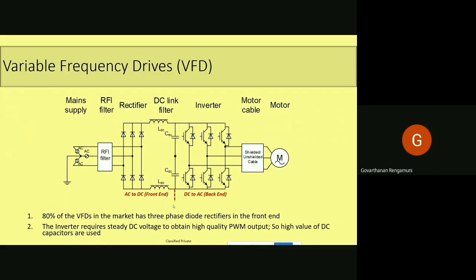The figure shows a typical variable frequency drive, and here different sections of the drive are noted. You can see the variable frequency drive derives the power from the mains. There is an RFI filter, and then a 6 pulse diode rectifier, and after that some LC filter. Then the conversion AC to DC happens. From DC to AC, there is a voltage source inverter, which consists of six IGBT switches, and the output will be a variable AC voltage which goes to the motor.